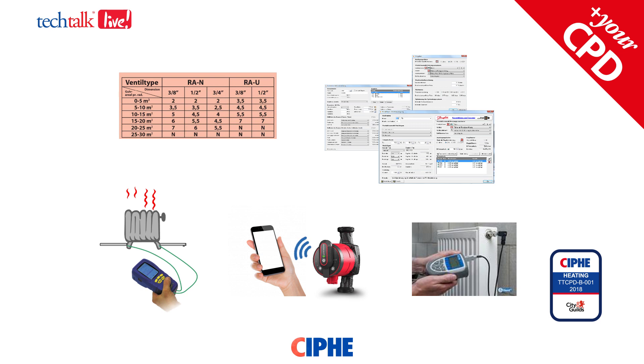There are some more advanced controls, generally used on commercial systems, where you actually build flow sensors into individual legs of the heating system. But this can be quite costly and prohibitive in a domestic application. Grundfos have the Alpha 3 system, which measures the flow to individual radiators and guides an installer through the process of adjusting valves and balancing via an app on a smartphone. This is quite easy and intuitive, and can reduce the time taken to correctly balance a heating system to between one and two hours on a typical system.